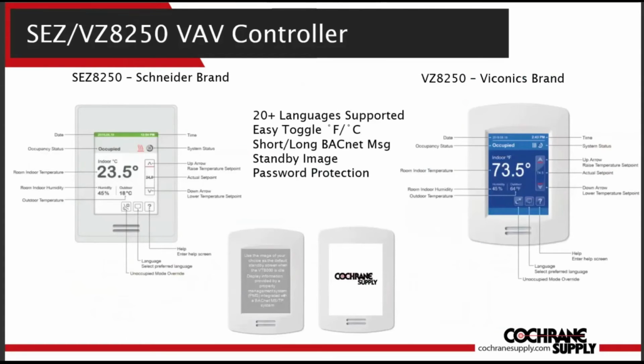Configurable as well. The display shows temperature and set point adjust. The heat symbol for heating mode, a snowflake for cooling mode. Fan operation is displayed by the fan symbol. You can choose to display the time and date, and which buttons appear on the bottom of the screen for operation: mode button for off, auto, degrees C, degrees F button, language button, unoccupied override button, and help button. Many times buttons are removed to limit the control occupants have over the operation of the equipment. You can also choose to display outdoor temperature, humidity, or CO2 level.